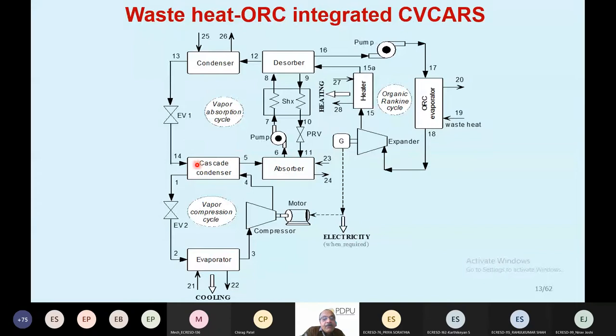So cascading means, here the operating temperature for the vapor absorption system is 5 to 7 degree, and the condenser rejects heat at 10 to 15 degree centigrade. The total temperature difference there is 10 to 15, while here it's minus 10. So drastically, more than 50% of compressor work is reduced. That is the main advantage.